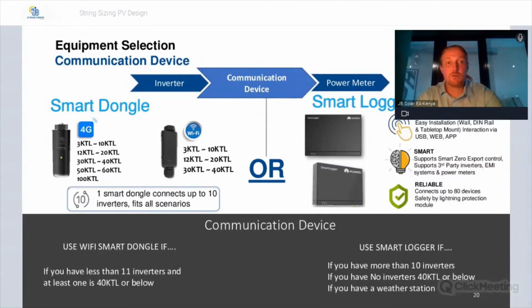If you can see there, it's compatible with all the inverters 40 KTL and below. Also, the smart dongle can manage up to 10 inverters. It cannot manage more than 10. If you have 10 inverters, you can use a single smart dongle. It's not one per inverter. Now, the smart logger works with all of the sizes above 40. It works with all of them as well, but for the 50 and the 60 and the 100, you will use a smart logger. Also, the smart logger can manage up to 80 inverters, 80. So it's for bigger installations.